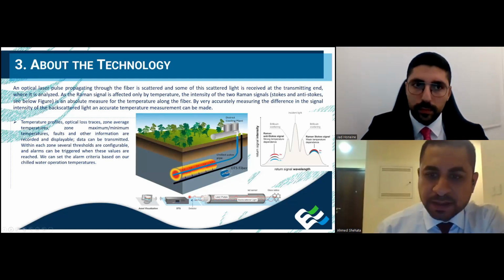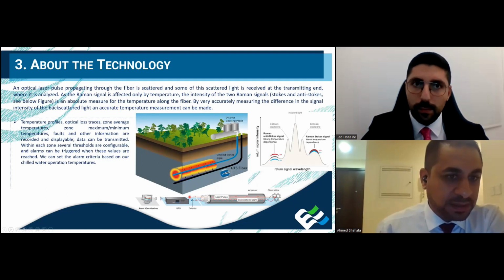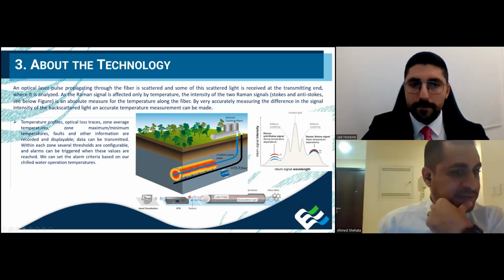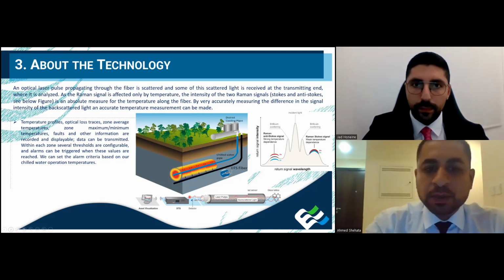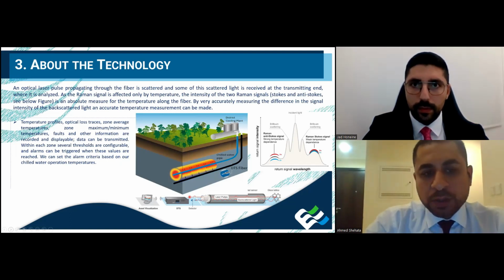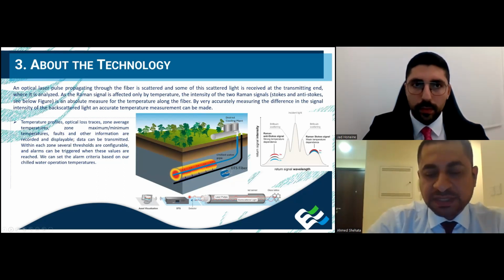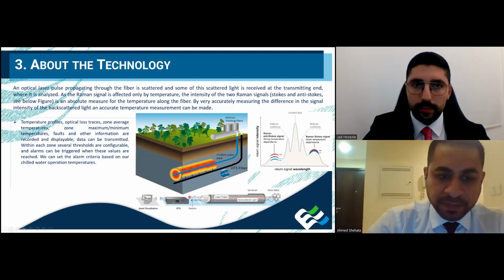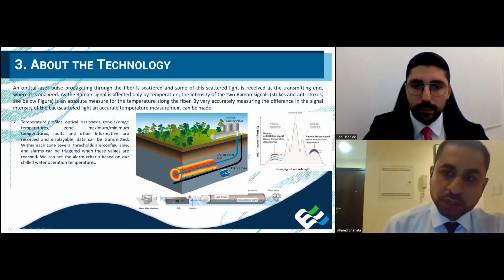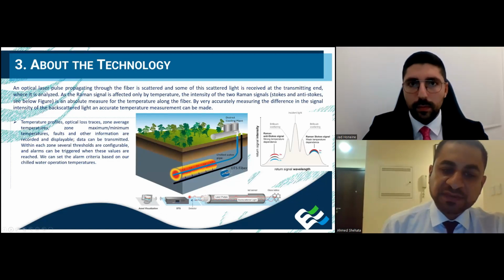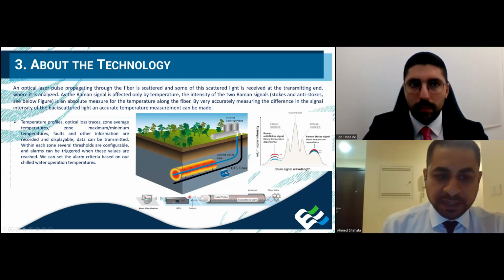I will explain about the technology and what we have exactly for the leak detection system. Emicool has a fiber optic cable network which runs along the chilled water piping network, mainly used for communication purposes. We use it for remotely reading the bidirectional meters and cooling meters from the customer end, required for billing, and also for remote monitoring and control of the energy transfer station at each building from the command and control center.